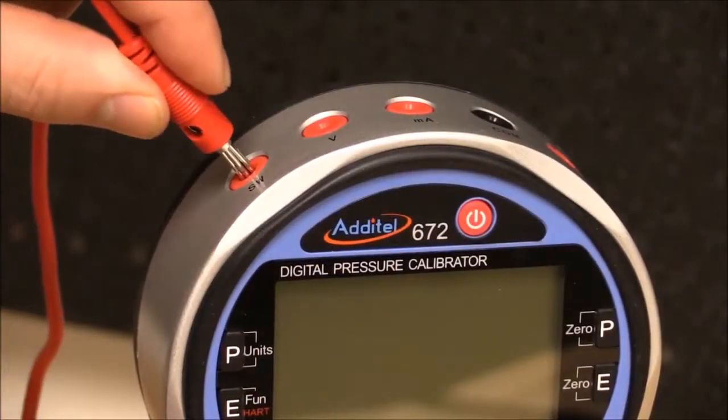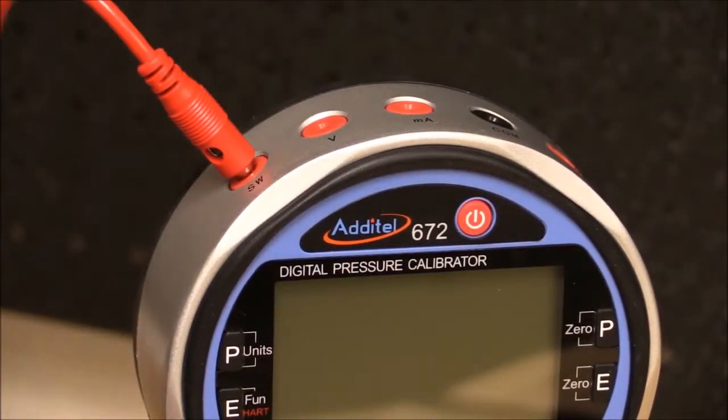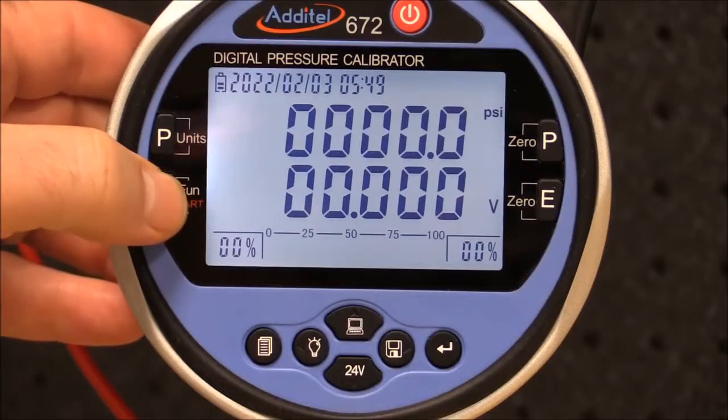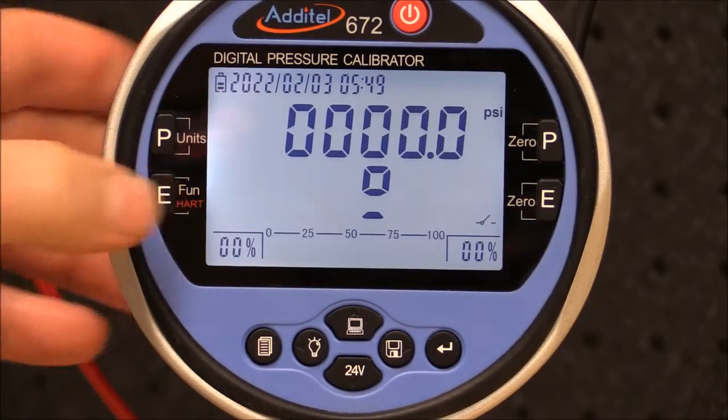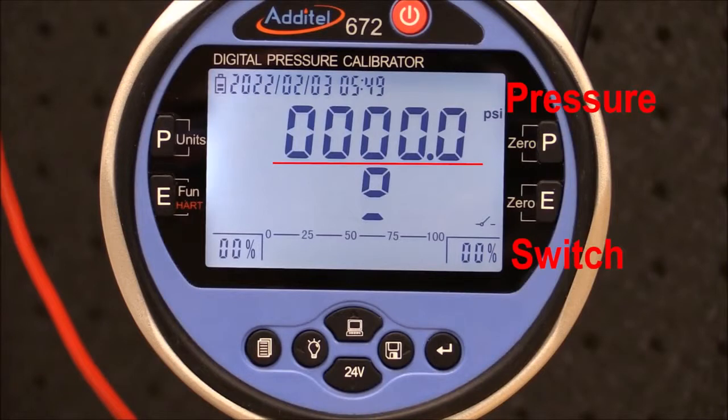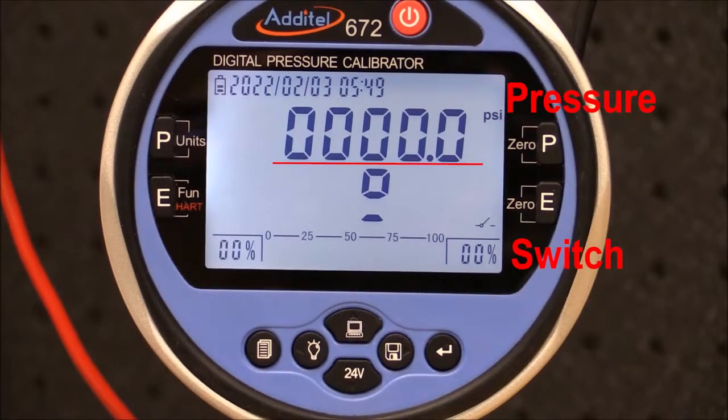The switch terminals can be connected directly to the Additel 672. To set up the ADT672, simply press the electrical function button until the switch icon displays in the bottom right corner. The dual display now shows pressure and the state of the switch contacts, which are currently open.